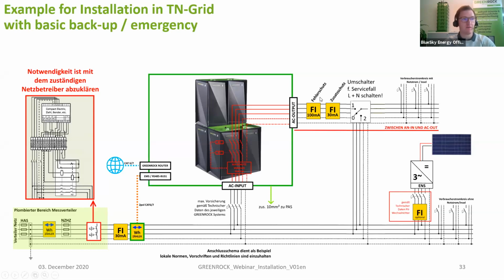But please always be aware of the maximum discharge values of a system, so that you ensure that the loads can run, stay active, and have not too much power to exceed the discharge power of the system. And what you can see here would just be an additional switch if you have some special loads connected here, and the Victron inverter has an error or a failure. Because in case of an error or a failure, the AC output is not powered anymore. So that's what the switch is for, so that you're able to switch these loads back to the grid in case of a system failure. This is really just an option which we recommend. It's not directly needed, but it's really a recommendation, so that in case of a system failure you can switch all these loads directly to the grid.